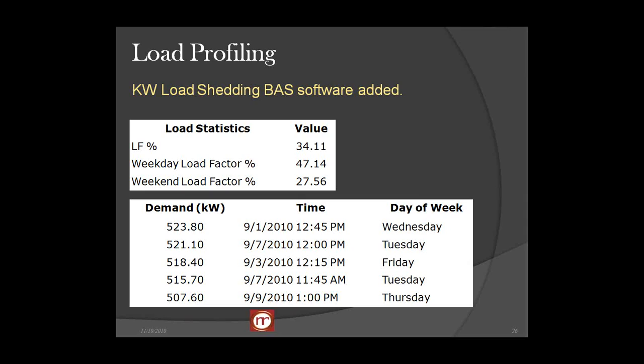I can also tell you that you need to dial your building in, and we were very conservative with this. We knew we had 640 kW, so we said, okay, load shed at 550. Then we saw that we were not using it that much, so we lowered it to 500. As of today, this building now sits at 460 kW, and we're hitting around 490, 500 kW because we don't have anything else we can shed with it. So we actually had this down to around 500 now, which we thought was outstanding. And we can carry that for 10 months out of the year.